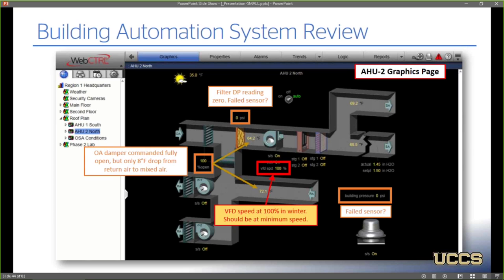And the VFD speed here was showing 100%, and this was a 35-degree day. So we really wouldn't expect it to be peaked out like that, but it may have something to do with the fact that in this case it was trying to economize. When I looked later, it did appear to be modulating like it was supposed to, so it could just be I grabbed it at the wrong time, but operating the fan at 100% is just going to lead to excessive fan speed and potentially additional reheat energy.